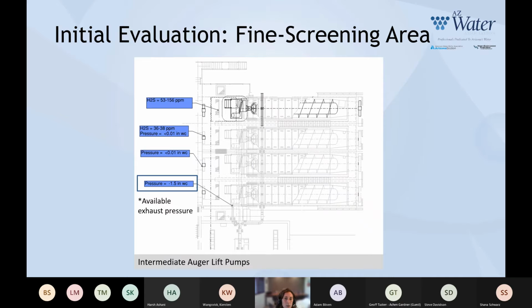The fine screen area and screw pumps include the screw pump inlet and outlet channels, fine screen influent channels, and fine screen building. Pressure and H2S data collected at the screw pump outlet channel is shown here in my blue boxes. As you can see, if you head up to maybe these middle two outlet channels, you see a slightly positive pressure, but actually down at the bottom of the picture here, you can see that there's a foul air duct that is intended to draw foul air from this channel.